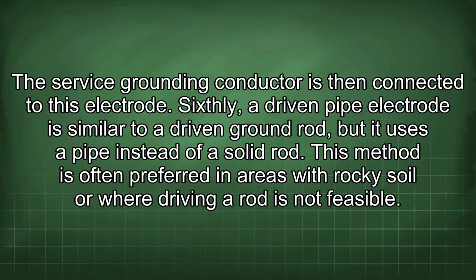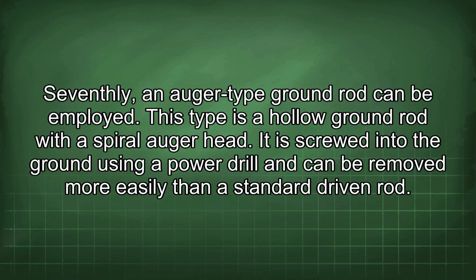Sixthly, a driven pipe electrode is similar to a driven ground rod, but it uses a pipe instead of a solid rod. This method is often preferred in areas with rocky soil or where driving a rod is not feasible. Seventhly, an auger-type ground rod can be employed. This type is a hollow ground rod with a spiral auger head. It is screwed into the ground using a power drill and can be removed more easily than a standard driven rod.